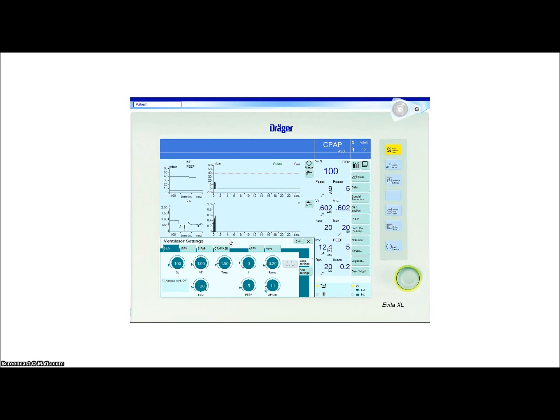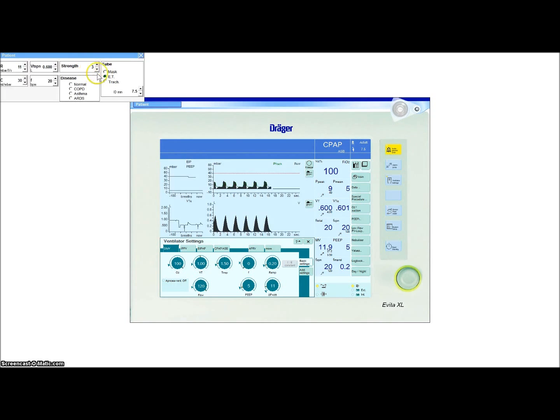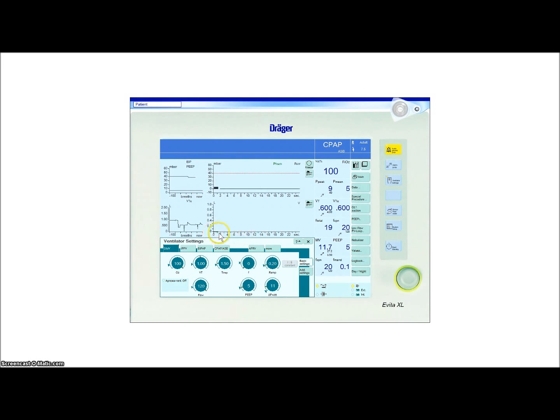That means this ventilation mode will not be able to support completely apneic patients. If he couldn't breathe, he would not be able to use CPAP. If you notice, he stopped breathing in SIMV and he still got a rate. If he stops breathing now, look at the waveform. Apnea. No breath rate. It's going to go down. We can configure an apnea ventilation backup, but we haven't done that. You'll see down here it says apnea ventilation off.